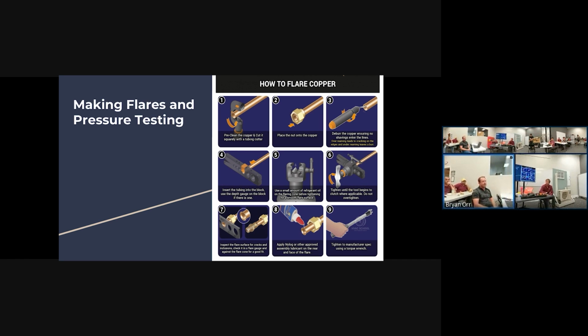This is a very specific product made with refrigerant oil. It will affect your torque specs. That always comes up. People always point that out. But again, we've done it. We've used it for a long time and still continue to tighten to spec, and we have good luck with that.